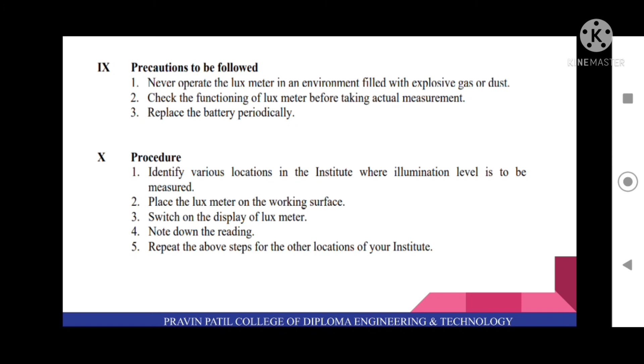In this practical, you have to write down the readings. For corridor, measured lux level is 104.3 and recommended lux level is 100. For library, 493.2 and recommended is 500. For staff room, 309.04 and recommended is 300. For laboratory, measured lux level is 510 and recommended is 500. For classroom, measured lux level is 502.09 and recommended lux level is 750.